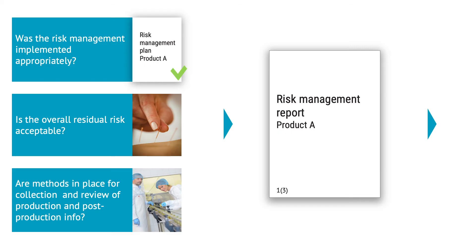The second question relates to whether the overall residual risk is acceptable. It might be that all individual risks are actually acceptable, but there are so many of them that you still cannot justify releasing the product to market. And lastly, are methods in place for collection and review of production and post-production information? Risk management doesn't end with the product development project — it is supposed to continue until your product is no longer used. You need to keep updating your risk management file using data from production, complaints, post-market surveillance, and updates to your clinical evaluation report.